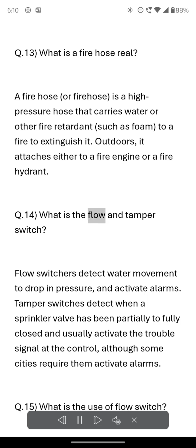Q.14. What is the flow and tamper switch? Flow switches detect water movement due to a drop in pressure and activate alarms. Tamper switches detect when a sprinkler valve has been partially to fully closed and usually activate the trouble signal at the control panel, although some cities require them to activate alarms.